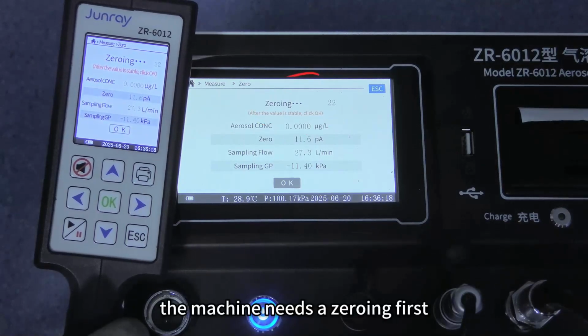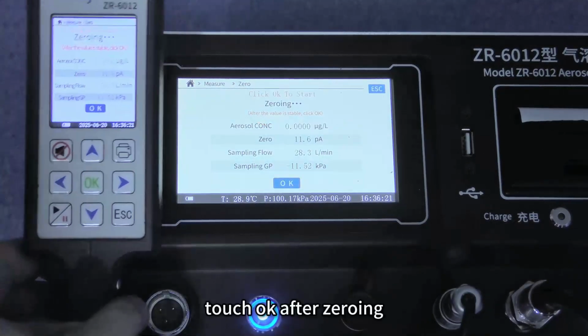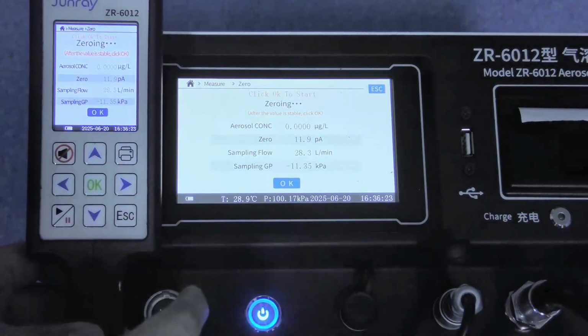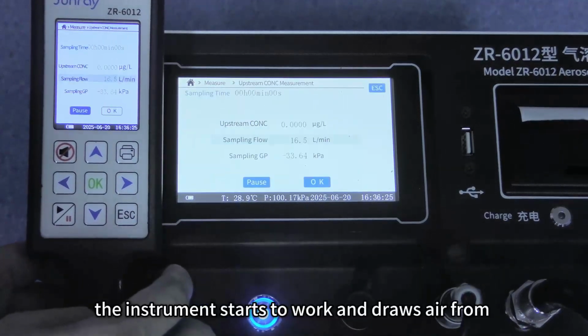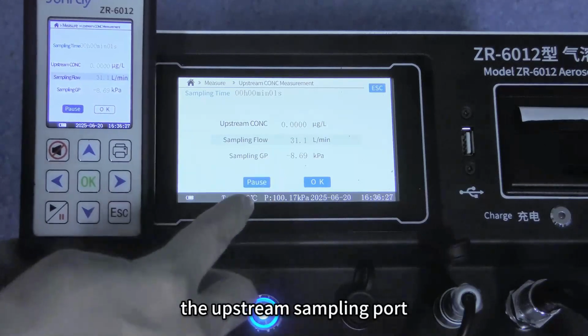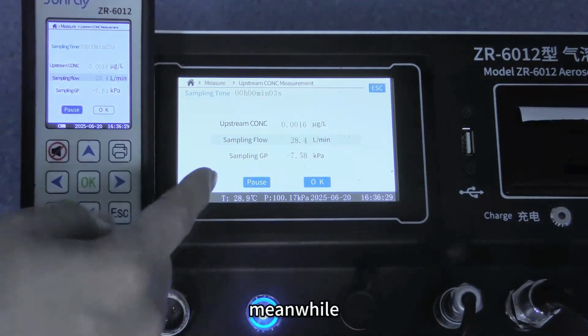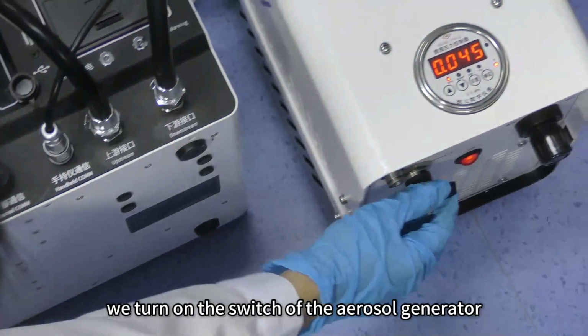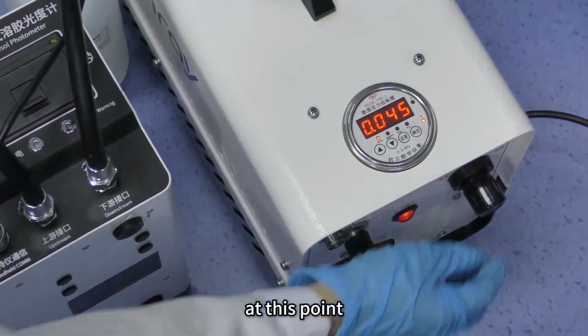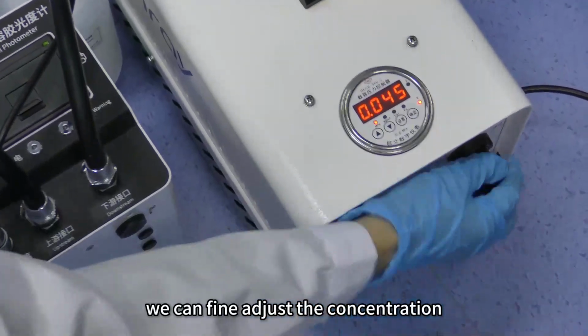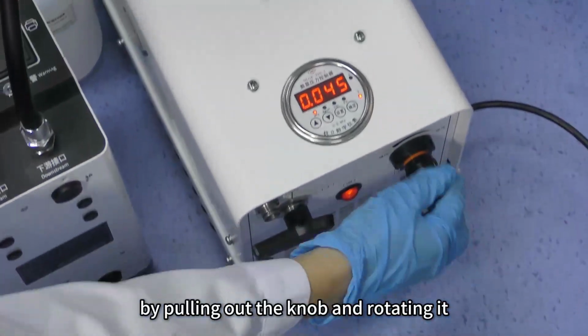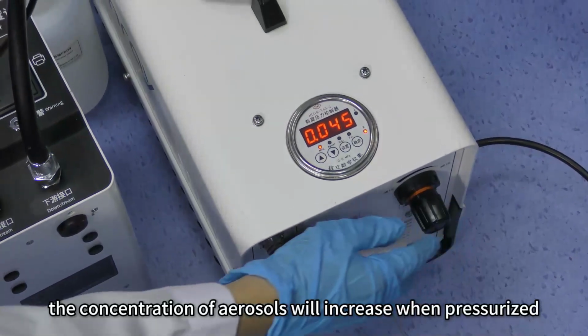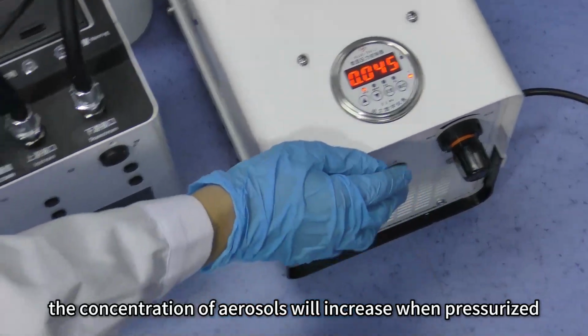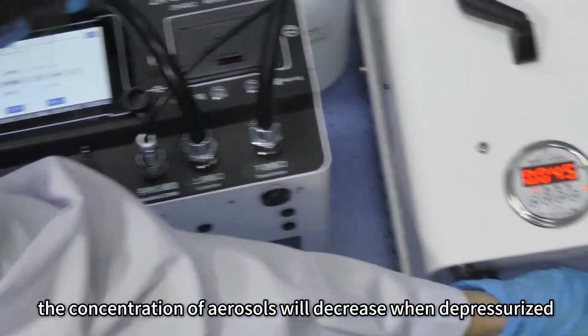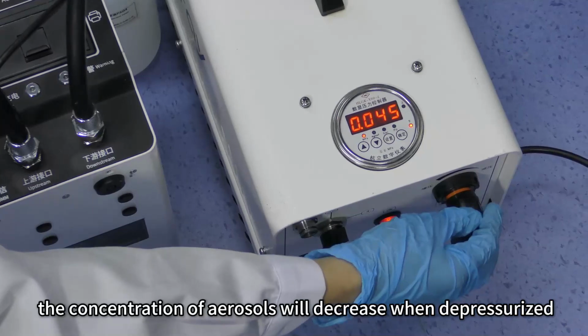The machine needs a zeroing first. Touch OK after zeroing. The instrument starts to work and draws air from the upstream sampling port. Meanwhile, we turn on the switch of the aerosol generator. At this point, we can fine adjust the concentration by pulling out the knob and rotating it. The concentration of aerosols will increase when pressurized. The concentration of aerosols will decrease when depressurized.